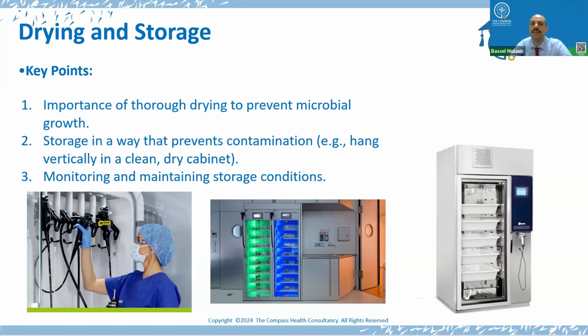You need to be ensuring that all adapters are removed. You need to dry the exterior of the endoscope with a soft, clean, lint-free towel, and dry accessible endoscope channels with a pressure-regulated instrument or pressurized air as per the IFUs. Do not attach removable parts during storage, and ensure that the endoscope is dried after every processing cycle, whether the intention is to store the endoscope or to reuse it immediately.